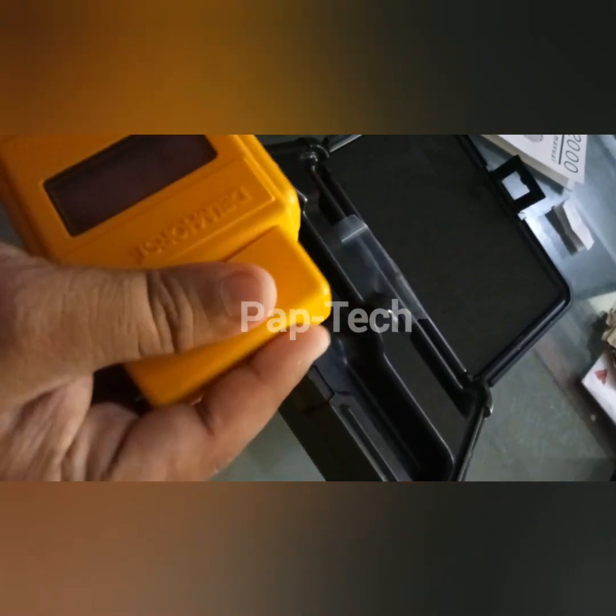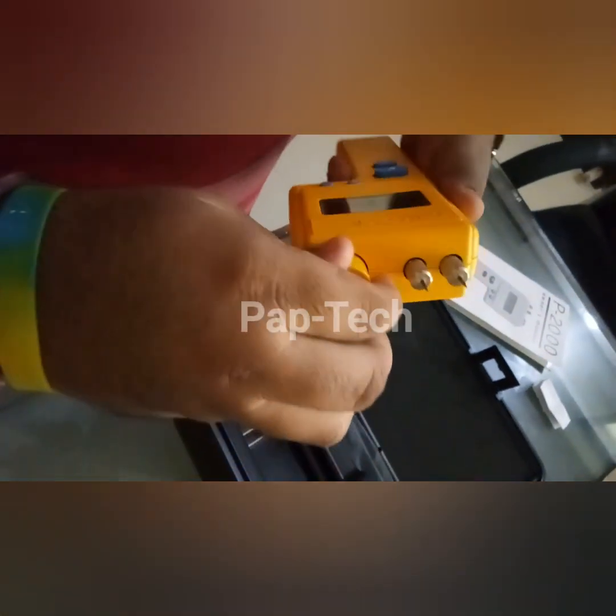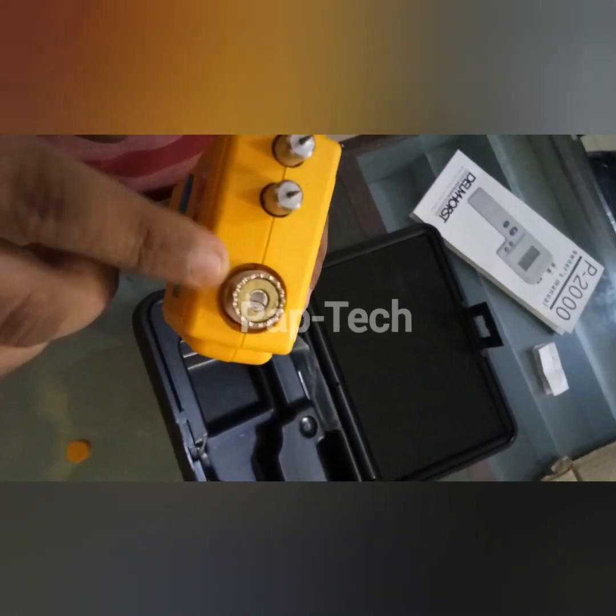The P2000 has different buttons — I'll show you how they work. Let's open its cap. These are the two pins used to check moisture. There is also another socket for an attachment, such as a roller used to check bale paper on a paper mill — that attachment can be connected here.